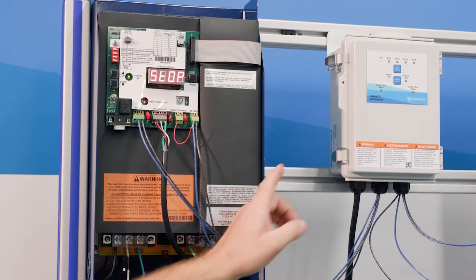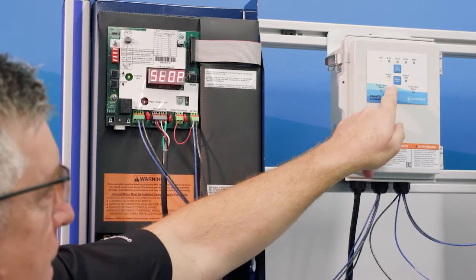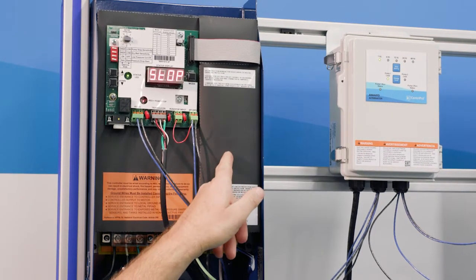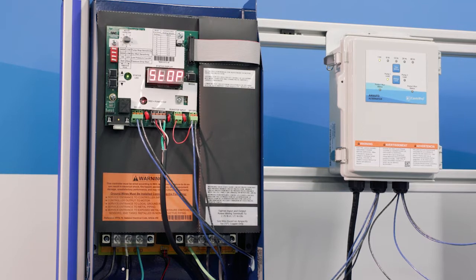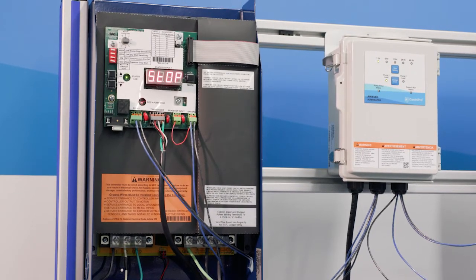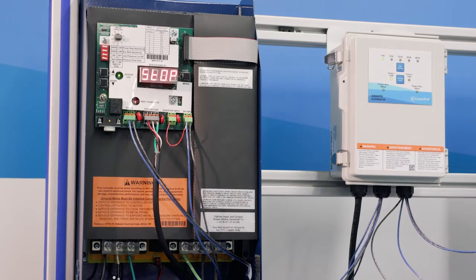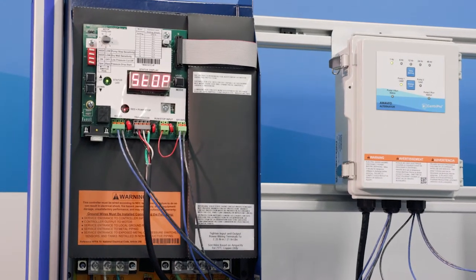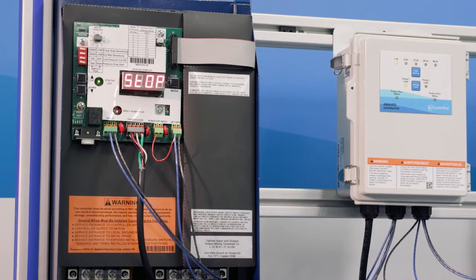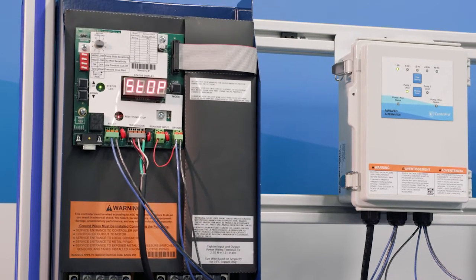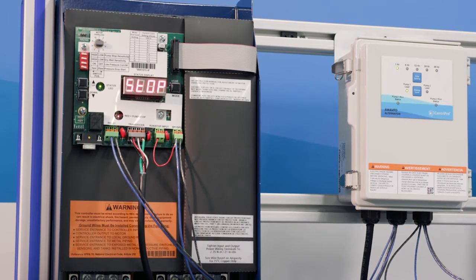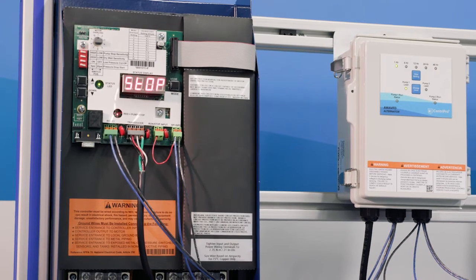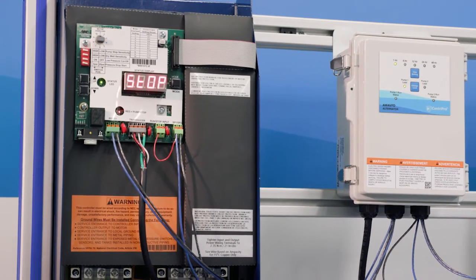So notice over here we have lead pump. Pump 1 is the lead. So this is set to lead right now. So we've got to set the set pressures, SP2 and SP1. I'd say one of the tricky things about this is SP2 is the lead. SP1 is the lag. That is the default. You could change that if you want, but right out of the box, SP2 is the lead. That's your higher pressure. SP1 is the lag. That's your lower pressure. You want those two to be at least 10 psi apart.